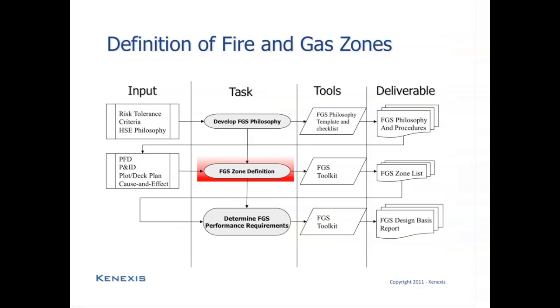The next step in the workflow for the design of fire and gas systems is going to be the definition of zones. Before starting out in the zone definition process, you're going to want to have a full understanding of the process that you're analyzing. This would include things like having process flow diagrams, piping and instrumentation diagrams, cause and effect diagrams for the fire and gas system if they have already been available at this preliminary stage or possibly for an existing facility. And most importantly, you're going to want a plot plan or a deck plan that physically shows where equipment is located in relation to the facility as a whole and with respect to other equipment. You're then going to want to use some sort of FGS design toolkit to develop the fire and gas zone list, which is going to be the output of this task.